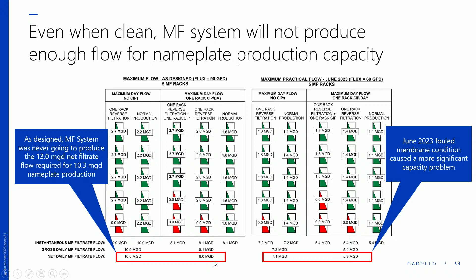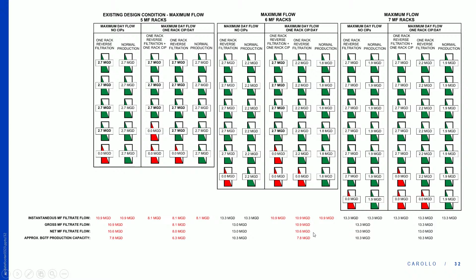So the question is, okay, what's the right number of MF trains? And I added this line here at the bottom, the nameplate production capacity. So the maximum capacity that's achievable with the current 5 MF rack arrangement is between 6.3 to 7.8 million gallons per day, depending on whether or not you're doing this cleaning on a particular day. If we add a 6th train, the flow rate improves. We can actually achieve the 13 million gallons per day needed, except for the days that the racks are going through a cleaning program. So 7 racks gets you the 13 million gallons per day needed to produce the nameplate production capacity.